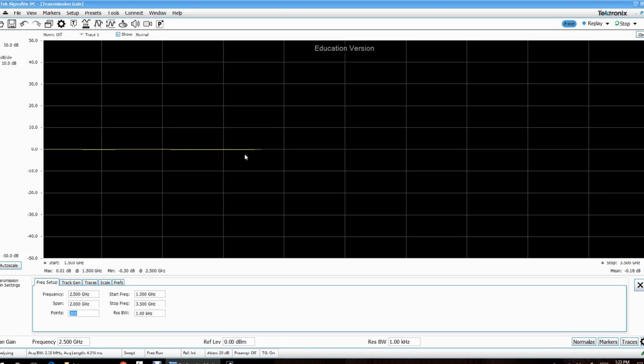Now, this is not as fast as I would have liked it to be. This instrument is not optimized for sweeping speed along very large frequency ranges. So it can be a bit frustrating if you have to do a live measurement and keep seeing the result as you're changing something, like if you're tuning a filter. But you can always change the number of points, the resolution bandwidth, depending on your needs. And for most of the time, it would be okay.